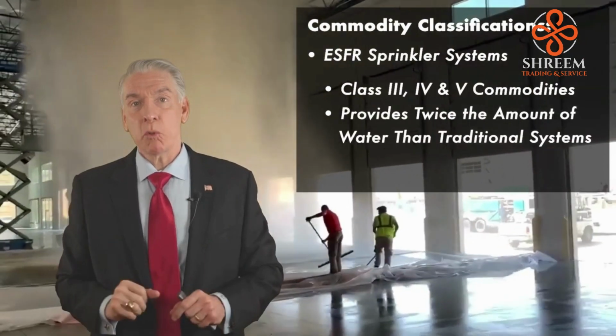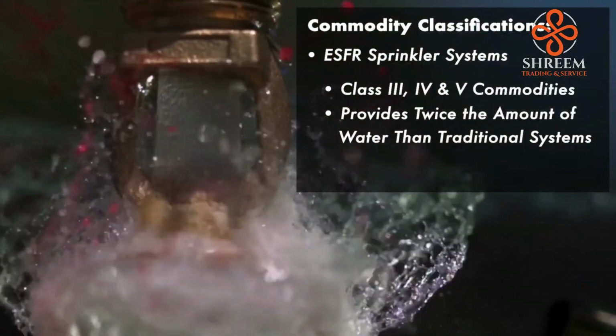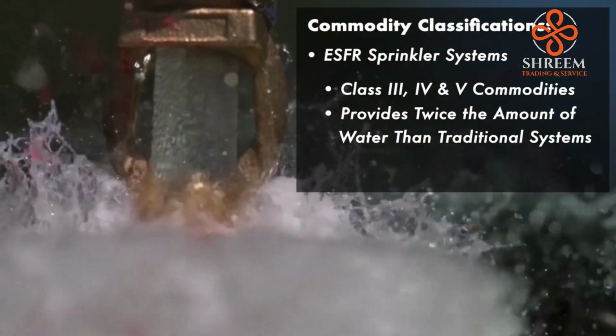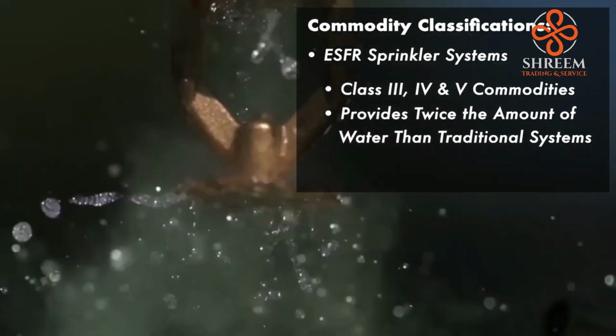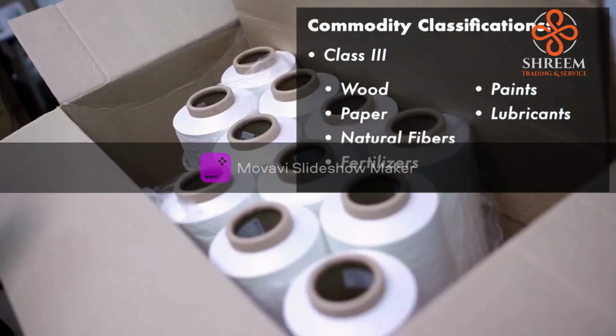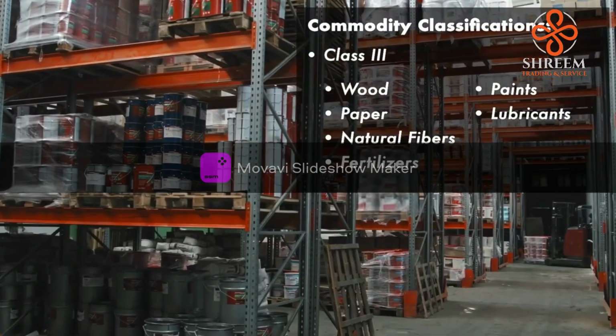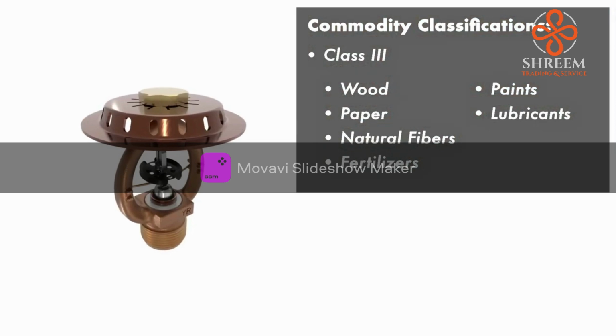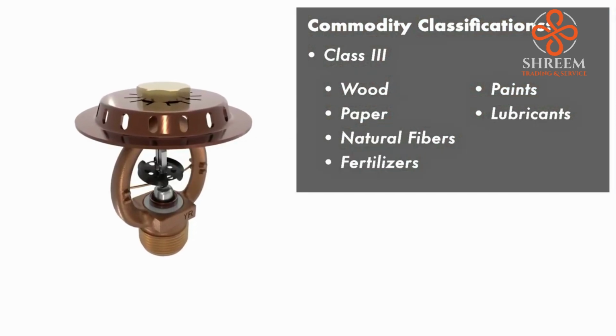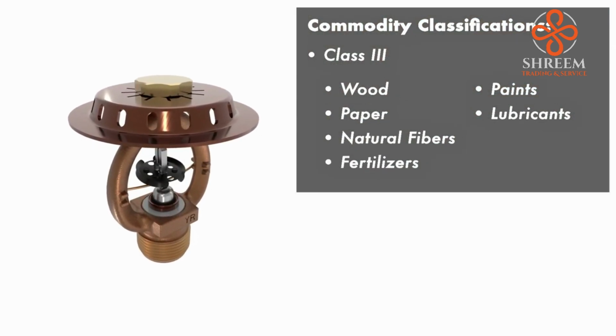ESFR systems provide at least twice the amount of water that traditional wet sprinkler systems do. For Class 3 products such as wood, paper, natural fibers, fertilizers, paints, and lubricants, you may be able to get away with a Class 3 ESFR sprinkler system. Considering the sprinkler system type will help you narrow down what sites to even consider seeing.